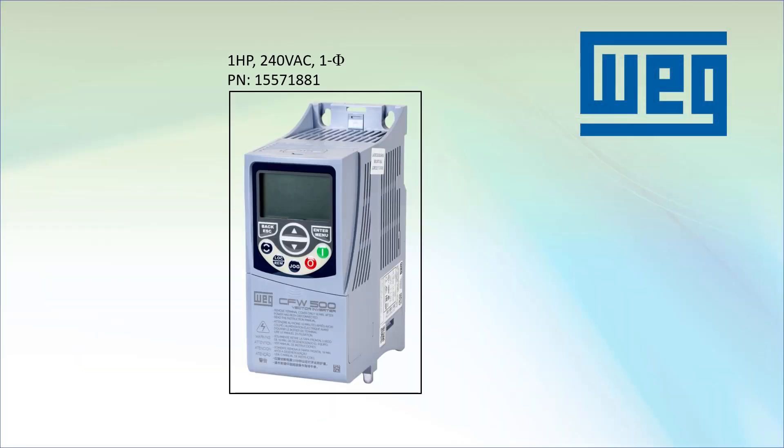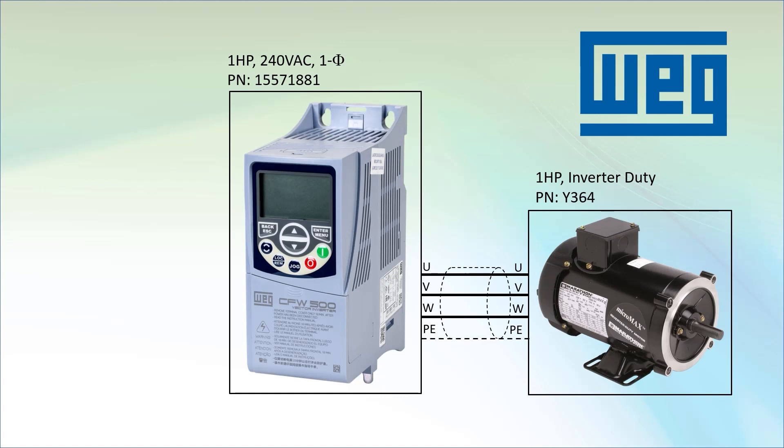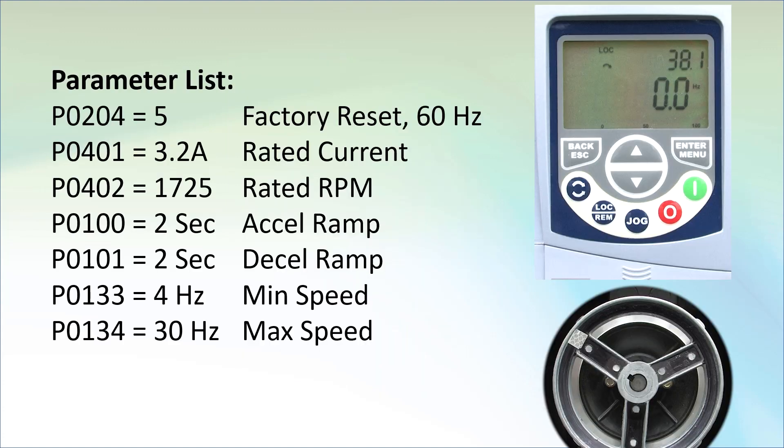Let's use this single phase 1 horsepower WEG CFW500 drive to control this 1 horsepower motor from a single phase 240 volt supply. Since this drive is designed specifically for single phase, you don't have to worry about derating. These are the parameters we're going to set and the values we're going to use to get the motor spinning in our demo.